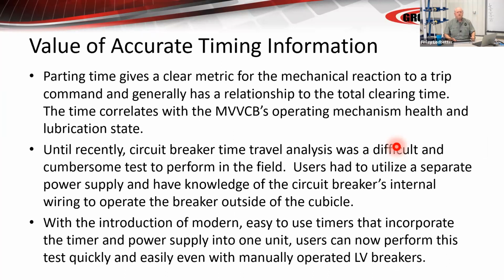Until recently, it was very difficult. There are modern timers today that are easy to connect. Doesn't take a real high-end person to get credible data. Think about timing results. Think about adding that into your breaker maintenance program, your switchgear maintenance program. Trend that to see if your lube is right, to see if your interval is right. If those times go up, it's a dead indicator. You either have a lubrication problem, an environmental problem, or your frequency of maintenance is too long.